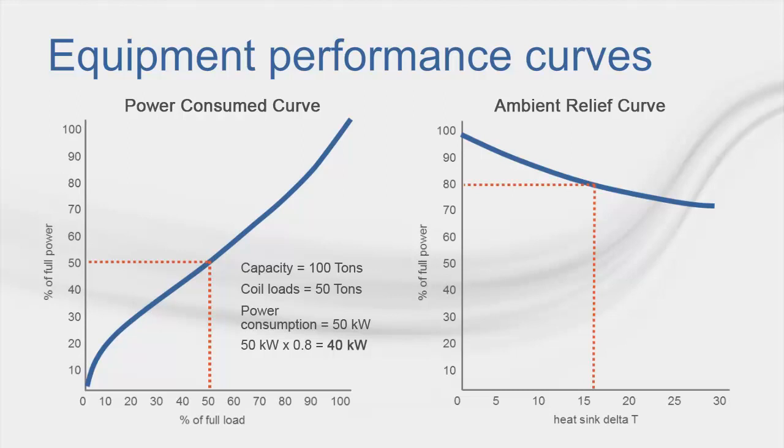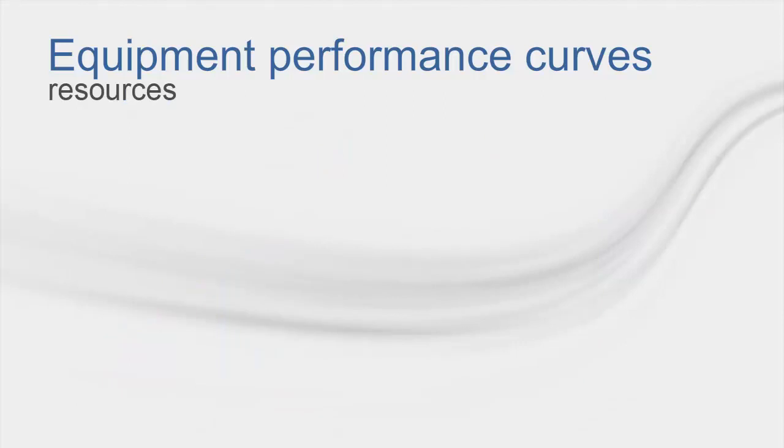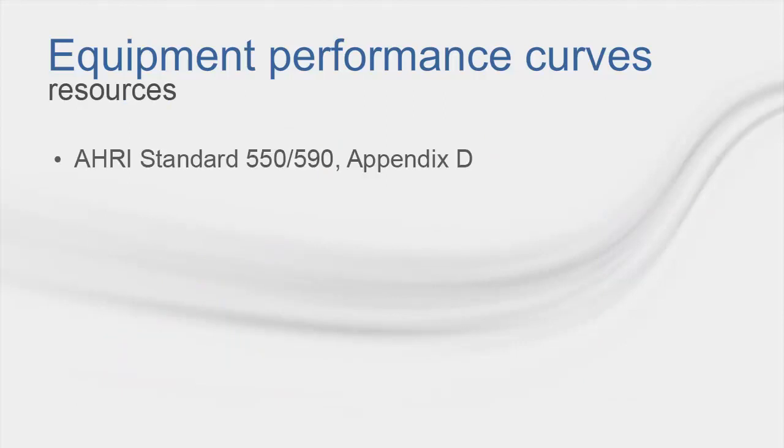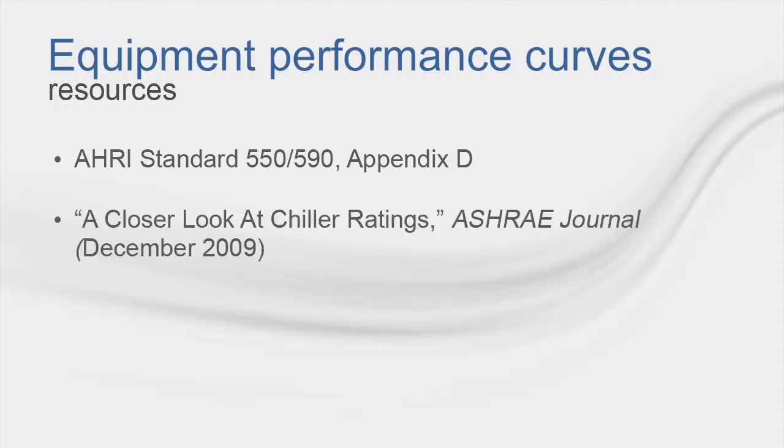IPLV and NPLV data where load and relief are co-mingled would be inappropriate to use because it does not allow for full computational analysis of equipment performance over a wide range of conditions. For further understanding on this subject, please refer to Appendix D of AHRI Standard 550-590 and to ASHRAE article, A Closer Look at Chiller Ratings, published in the December 2009 ASHRAE Journal.